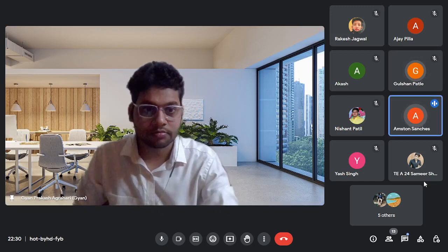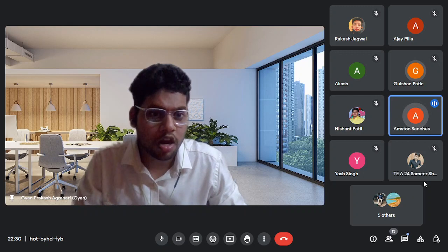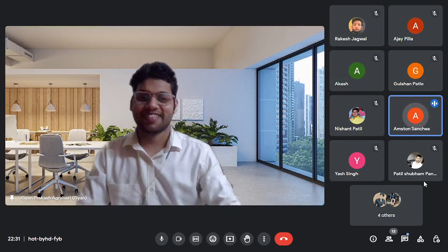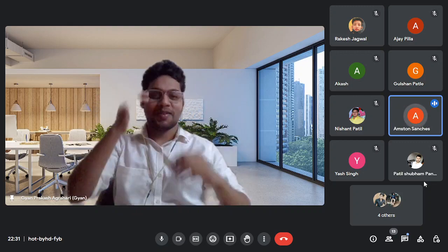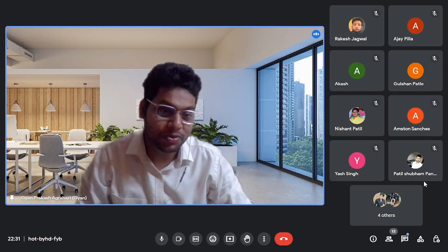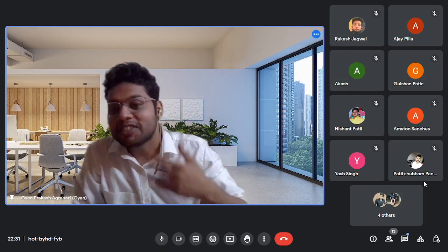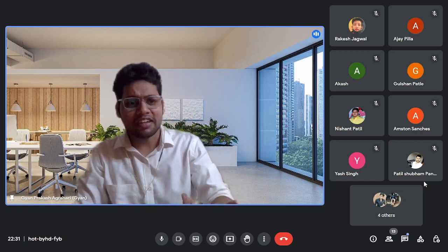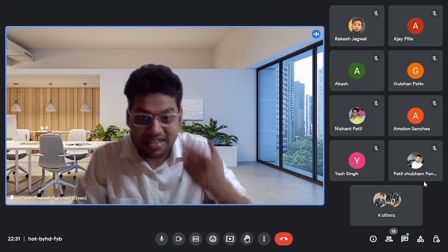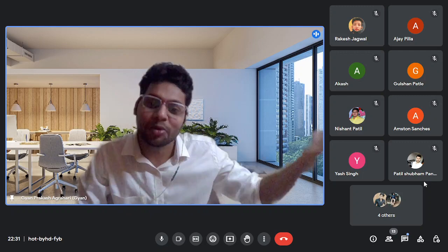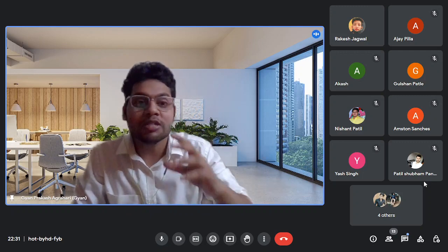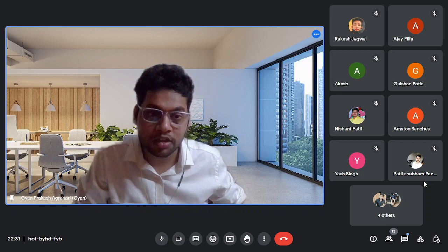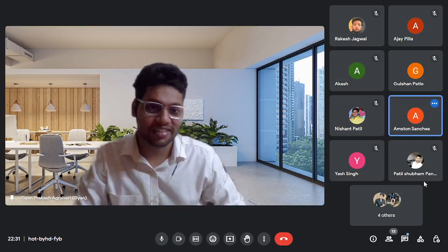Gyan, I had a question for you. A centrifugal pump is used where flow is required, right, and not much pressure? And here you are saying that at the discharge side you get more pressure than kinetic energy. So how does this really work? This was my question also. If a centrifugal pump is required for high discharge and not very high pressure, why is there a need to create pressure at the discharge side? No, there is a need for pressure at the discharge side. Otherwise, how will the fluid flow? But this pressure is not that high in comparison with a positive displacement pump.